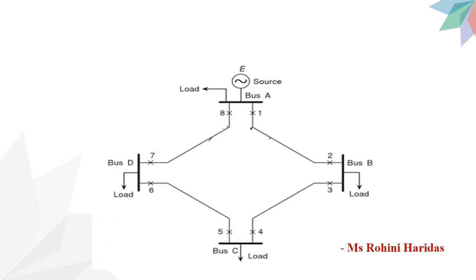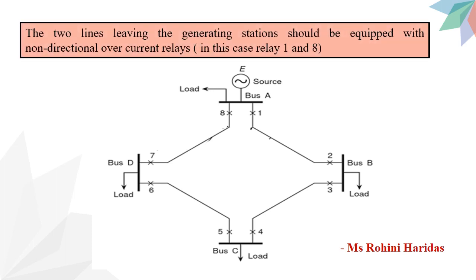Now let us discuss the time-graded overcurrent protection applied to the ring-main system. In this arrangement, power can flow in both directions under fault conditions. Therefore, it is necessary to grade in both directions around the ring and also to use directional relays. In order to achieve selectivity — isolating only the faulty section — we have to follow certain rules.